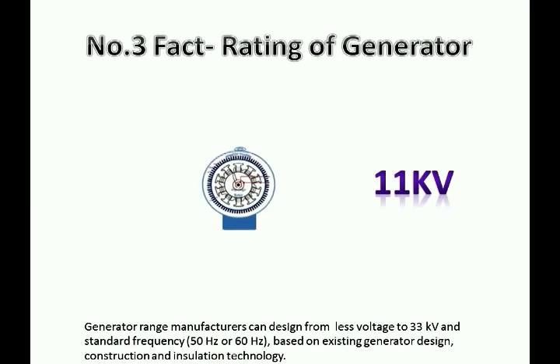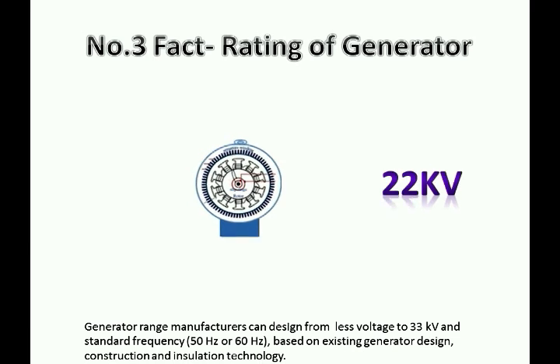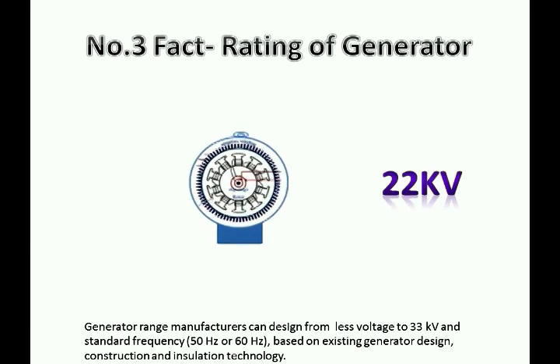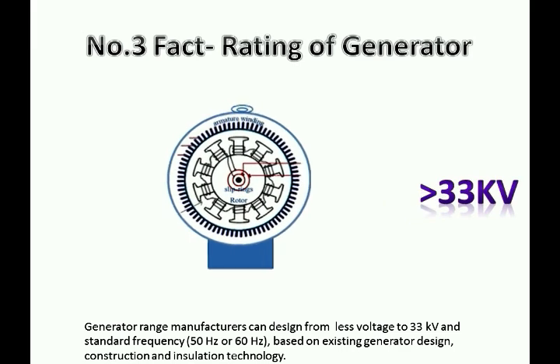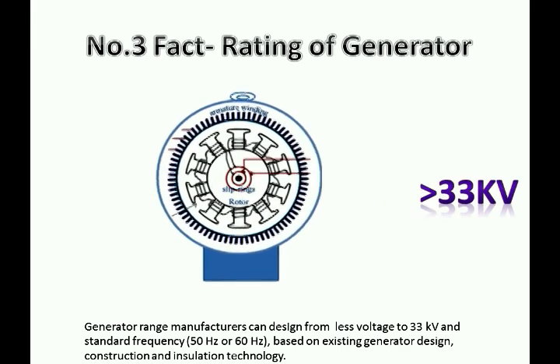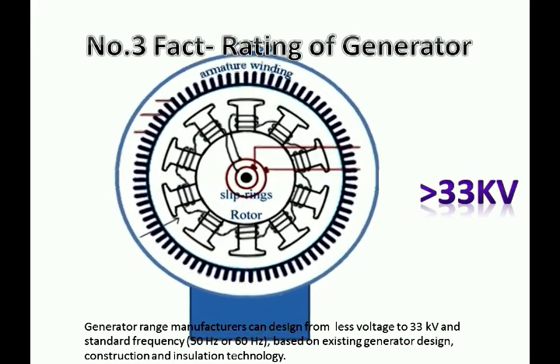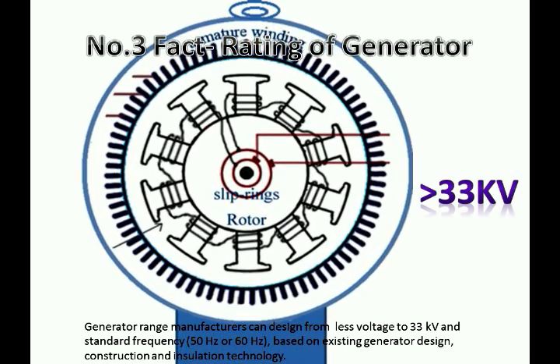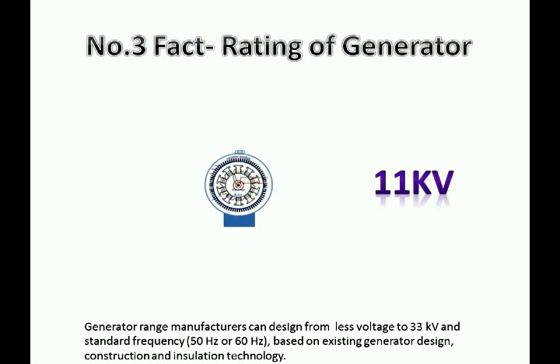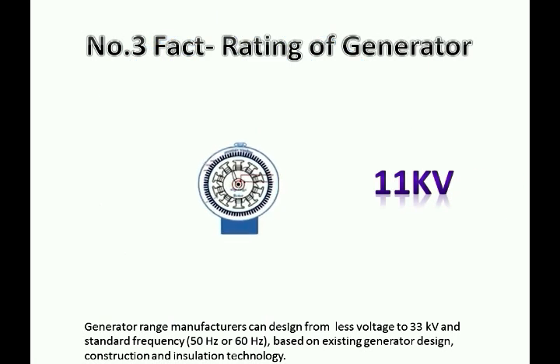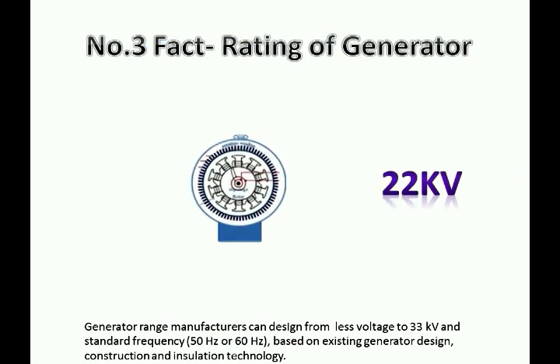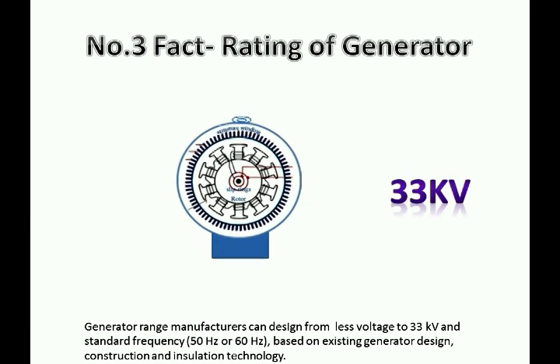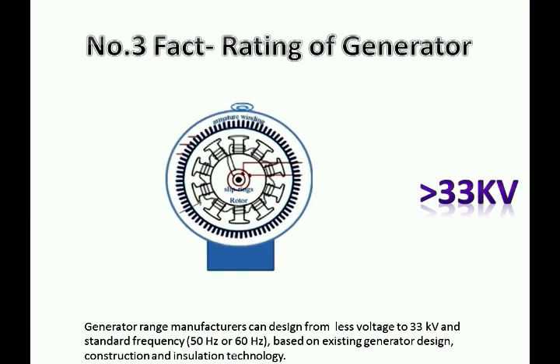Third interesting thing: a generator manufacturer can design a lesser voltage up to 33 kV, and the standard frequency is 50 Hz to 60 Hz. Why does the power station range from 11 kV to 33 kV? Let us consider if the generator capacity is 100 MW. If we use an 11 kV generator, the current in the stator will be very very high compared to the 33 kV generator. And also, if we reduce the current level, then the copper loss will also reduce.